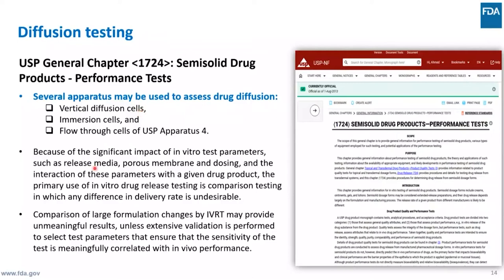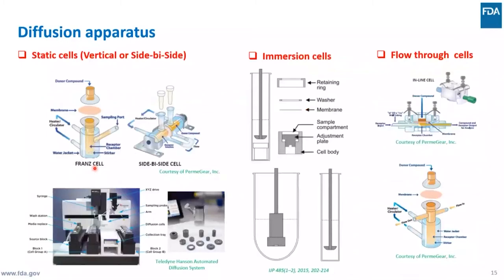Several apparatus are mentioned in the chapter, including vertical diffusion cells, immersion cells, and the special flow-through cell used in USP Apparatus 4. Because of the significant impact of in vitro test parameters, the primary use of in vitro testing is mainly for comparison testing, where any difference in release rate is undesirable — such as bioequivalence testing of test versus reference drug products, lot-to-lot variability, and product changes at different levels. Comparison of large formulation changes by IVRT may provide unmeaningful results unless extensive validation is performed.